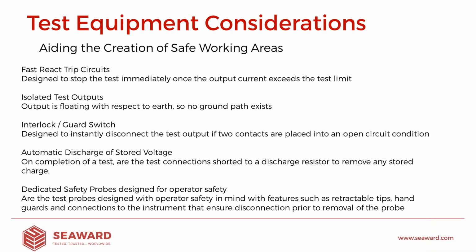We alluded to interlocks a little bit earlier when we were talking about the enclosure scenario. Most testers nowadays on the market will have an interlock feature, or a guard switch as we call it within Seaward, and they're designed to instantly disconnect the output if the two contacts of the switch are placed into open circuit. So effectively a guard switch is very, very simply two contacts that need to be shorted together in order for testing to go underway.